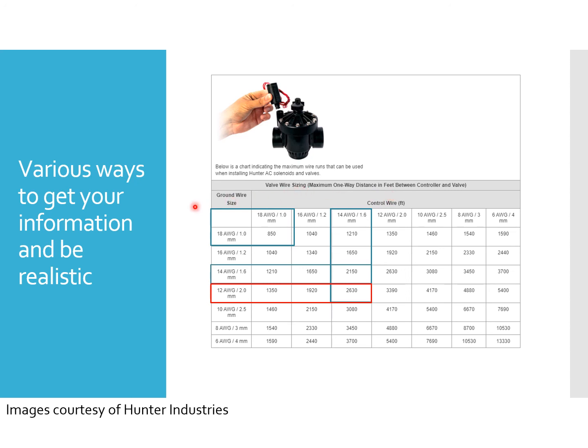So here they're saying maximum one-way distance in feet between the controller and their AC valves is, if you're using 18 gauge wire for your ground and you're using 18 gauge wire for your common, the furthest you can go is 850 feet. Now, if you were using a 14 gauge wire for your control and a 14 gauge wire for your common, you can run up to 2150 feet. Now, if you needed a larger ground and you went with a 12 gauge ground and a 14 gauge control wire, you can run up to 2,630 feet. So that's another way of doing it.